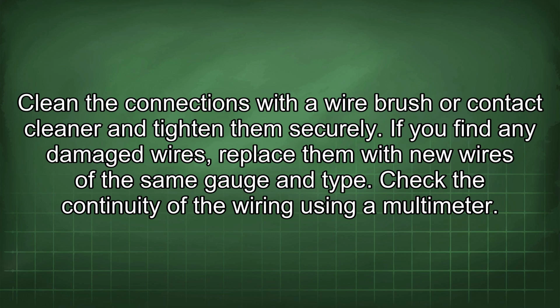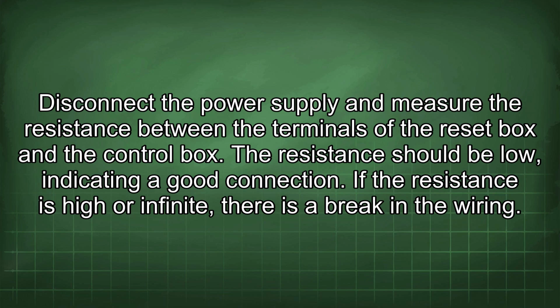Check the continuity of the wiring using a multimeter. Disconnect the power supply and measure the resistance between the terminals of the reset box and the control box. The resistance should be low, indicating a good connection. If the resistance is high or infinite, there is a break in the wiring.